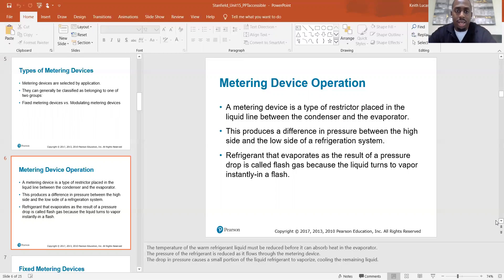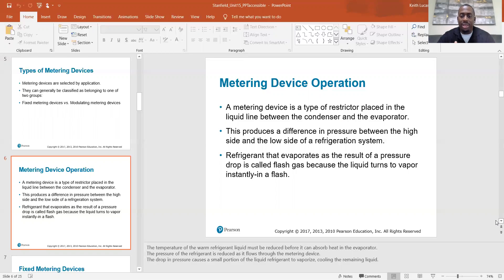A metering device is a type of restrictor placed in the liquid line between the condenser and the evaporator. This produces a pressure difference between the high side and the low side of a refrigeration system. Refrigerant that evaporates as a result of a pressure drop is called flash gas, because the liquid turns to vapor instantly — in a flash. The temperature of the warm refrigerant liquid must be reduced before it can absorb heat in the evaporator.